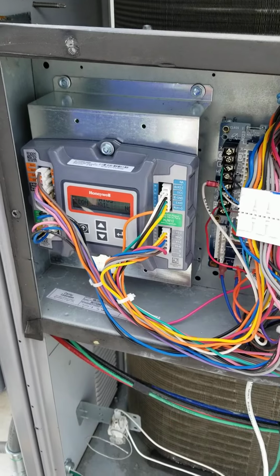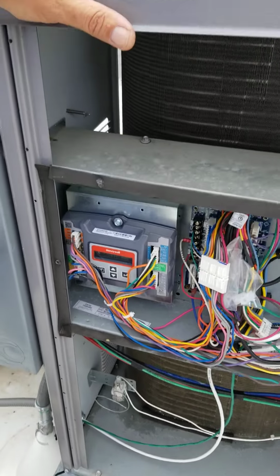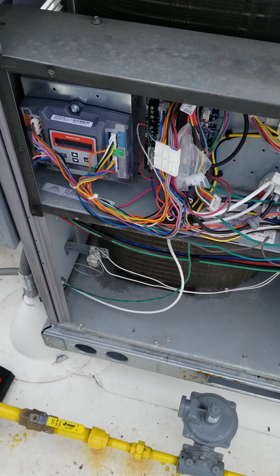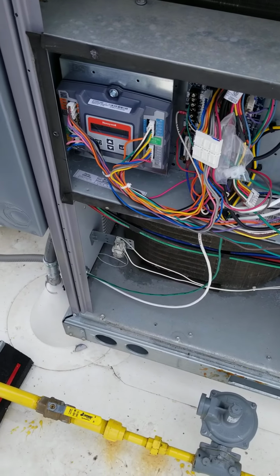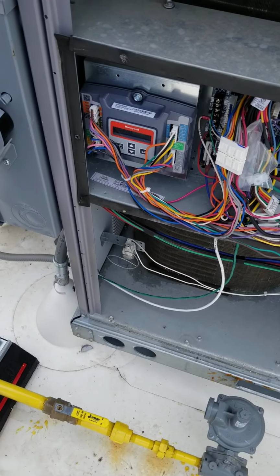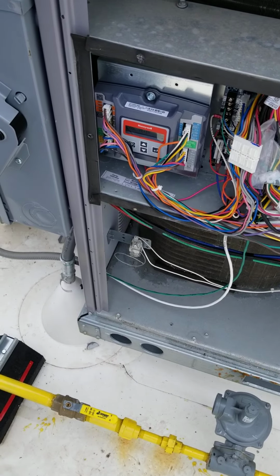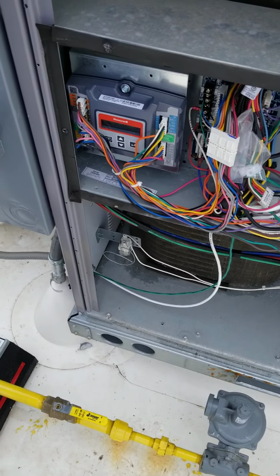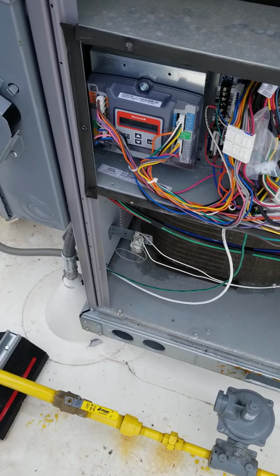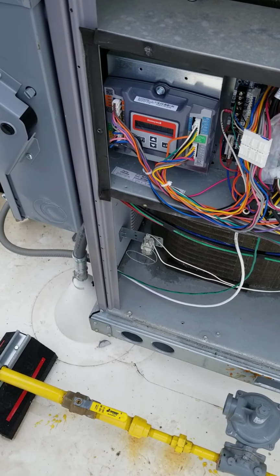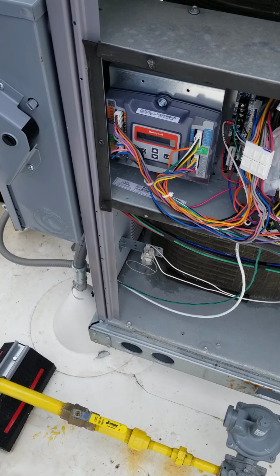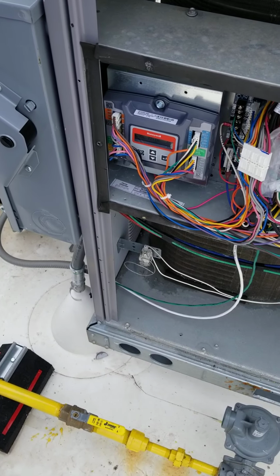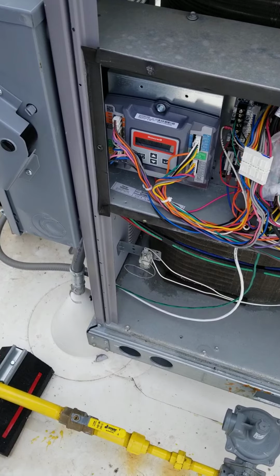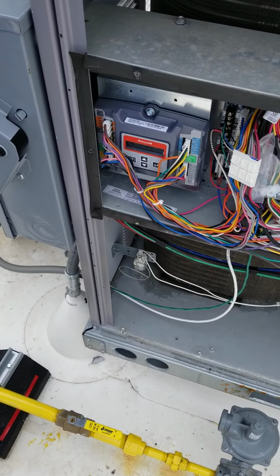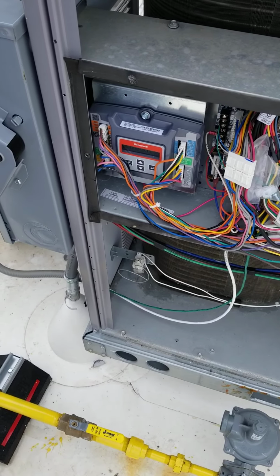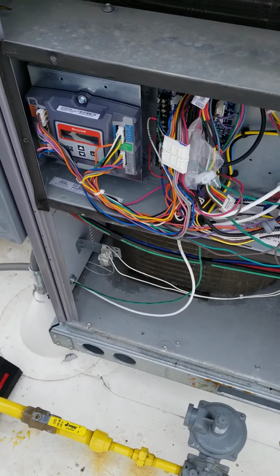The economizer is set for 60 degrees. So anytime we're below 60 degrees, if there's a call for cooling, the unit will decide it can satisfy that call with the economizer using free outside air instead of running compressors. But let's say if we're at 60 degrees and it's 30% humidity, it'll use outside air. If we're at 60 and it's like 80% humidity, there's a control in there that says we're not going to do that - let's run mechanical cooling instead, because it's kind of like on a curve, with enthalpy control.